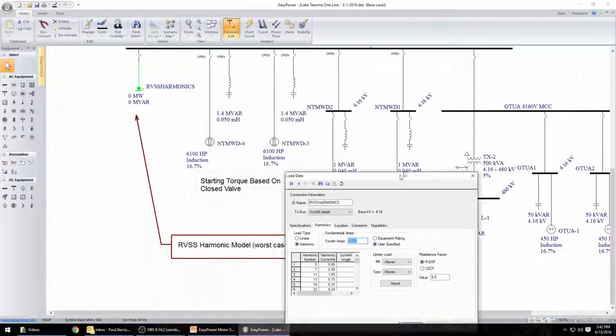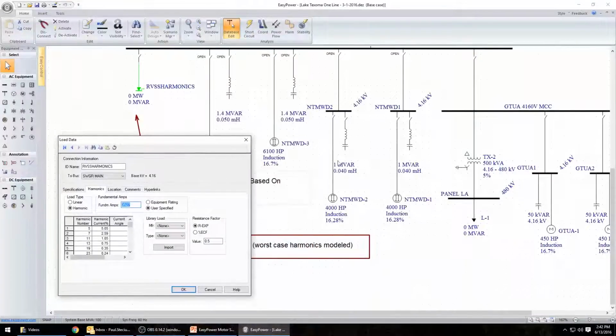If I were to double click on that bus behind that harmonic load device, you can see that we have a fundamental current of 3527 and also some harmonic current percentages plugged in here. These are based upon the slide that I presented earlier, the worst case harmonics at each possible phase angle. And what we do is we're looking just to capture the worst case situation to make sure that during a soft start application the soft starters will not negatively react with these capacitors here, or for the case of an actiVAR start, won't negatively react with the actiVAR itself.